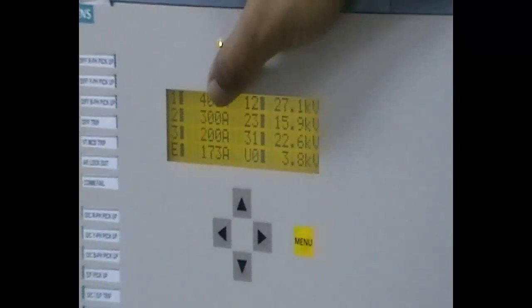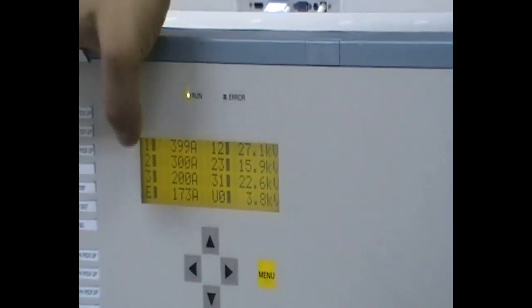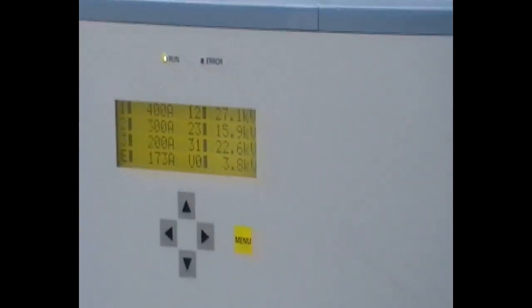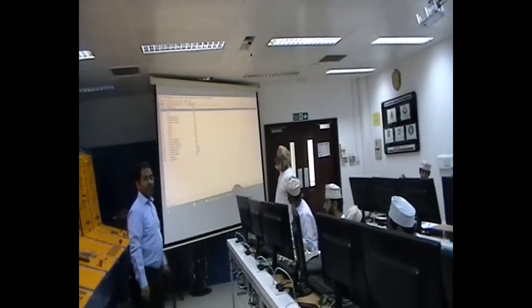What is the red phase? At least the voltage. Now here, if you can see, is the imbalance reading: red, yellow, blue, and neutral. 400, 300, 200, and imbalance 173 ampere. So that is what it shows here. If you have unbalance, you will have positive, negative, and zero sequence components, which are given here.